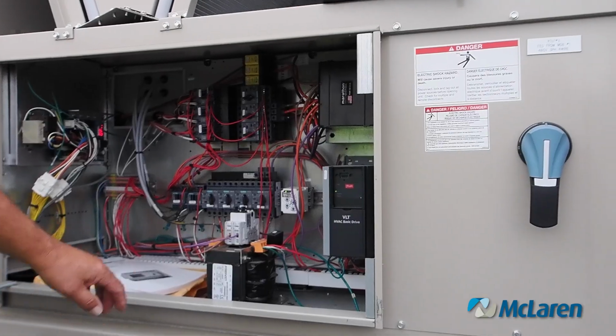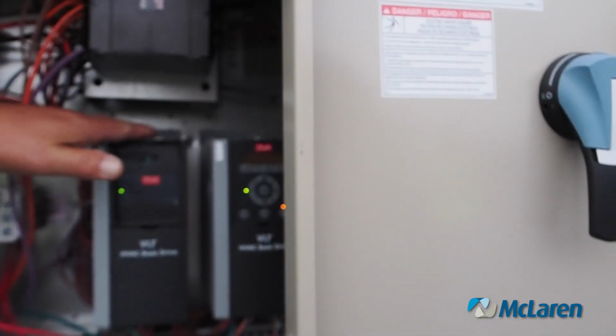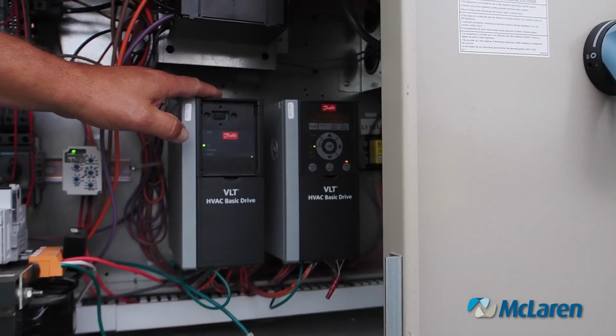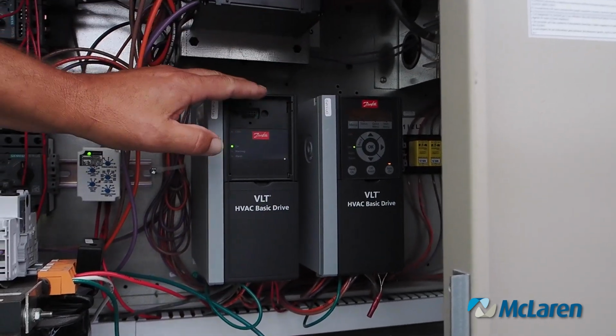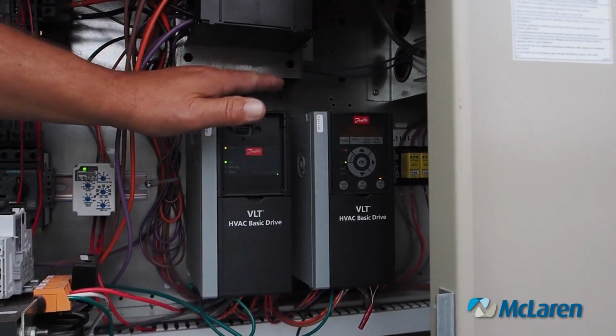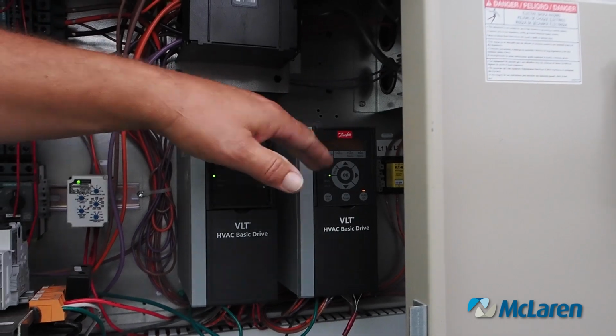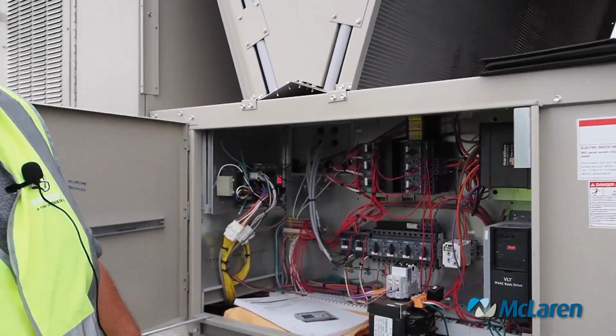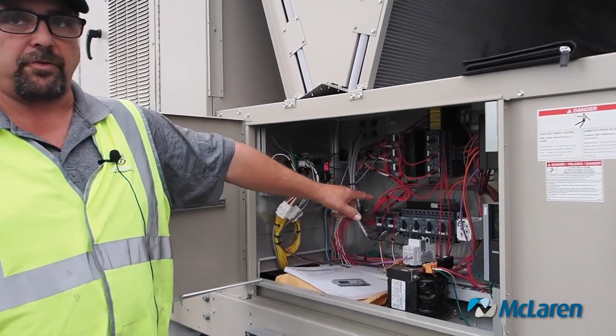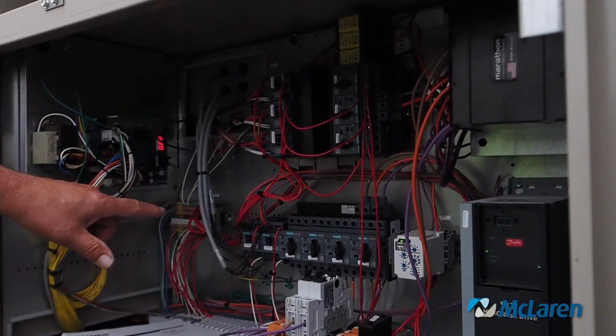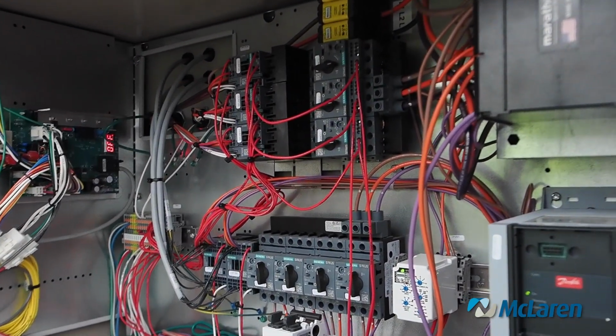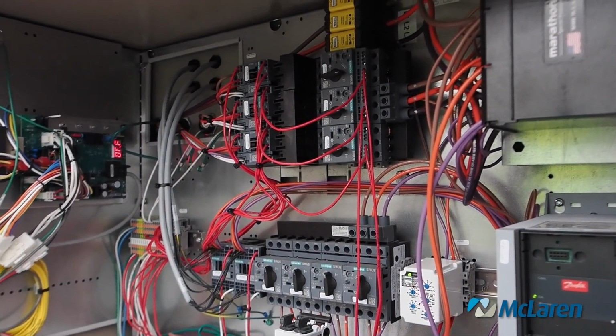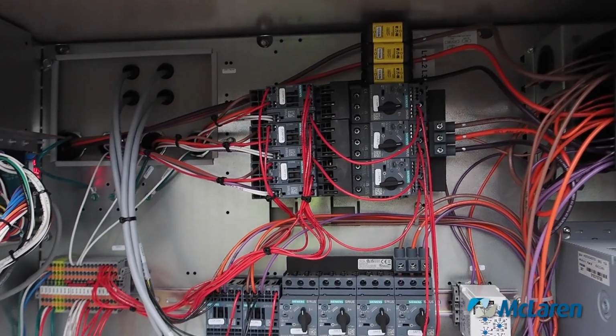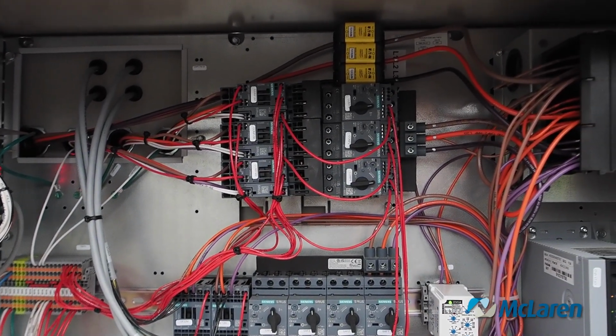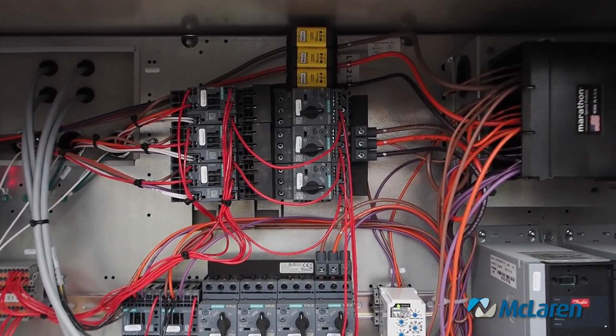Also, you have these 2 condenser fan drives. Yes, there is a screen missing, but they do not supply another screen. This screen pops out and can be put onto this drive too. It's transferable. That's why there's only one display. These are the condenser fans. Here are your overloads for your motors and fans. And I like to point out the word tripped on them. They're at the 10, 11 o'clock position if you're looking straight at them. If an overload trips, please shut the unit down, kill power, and then reset it.